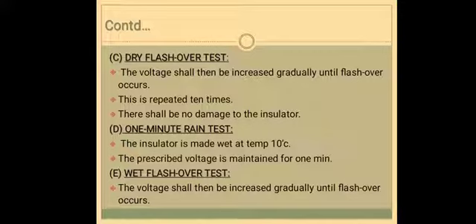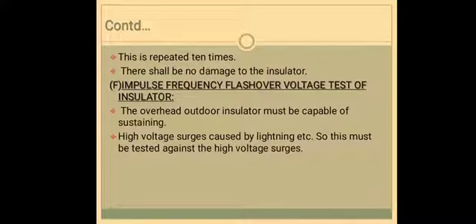Then next is the wet flashover test. In the wet flashover test, the voltage shall be increased gradually until flashover occurs. This will be repeated 10 times and is also similar to the dry flashover test. There should also not be any damage to the insulator.